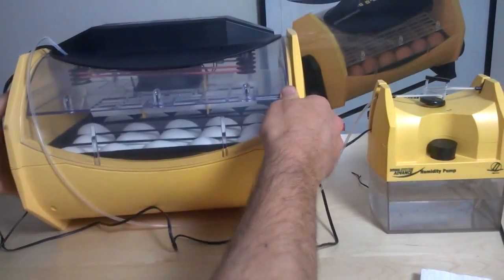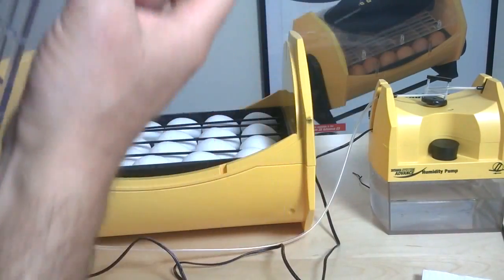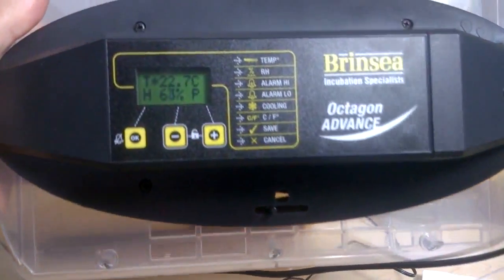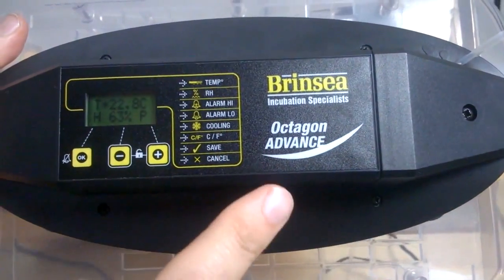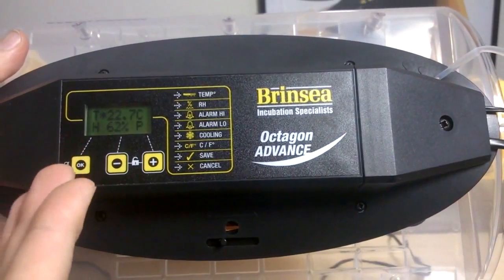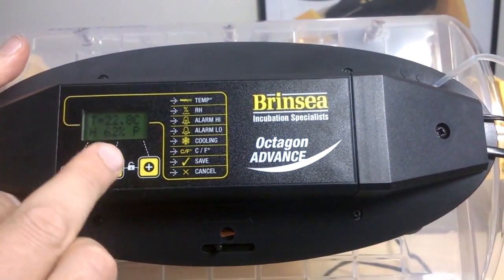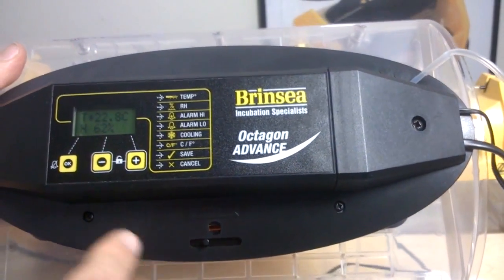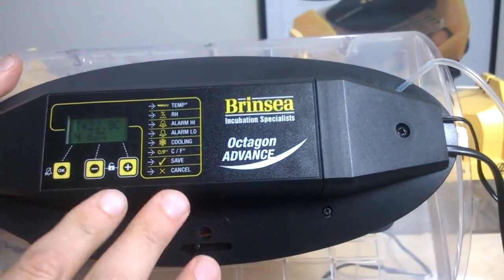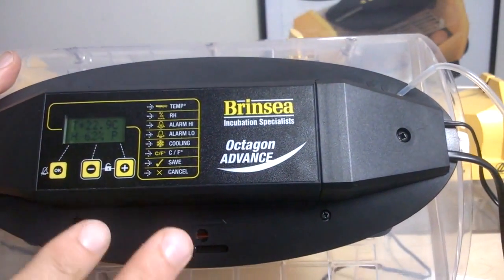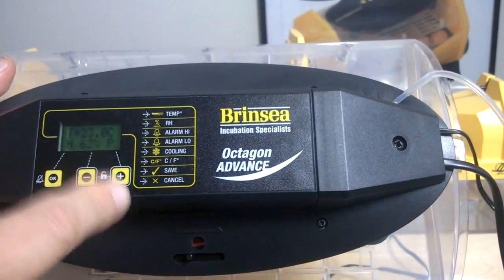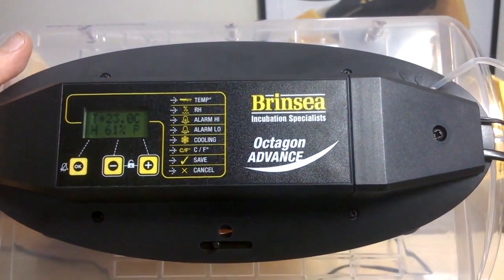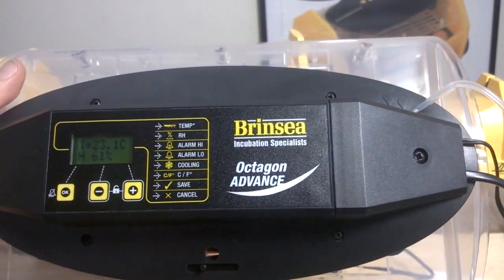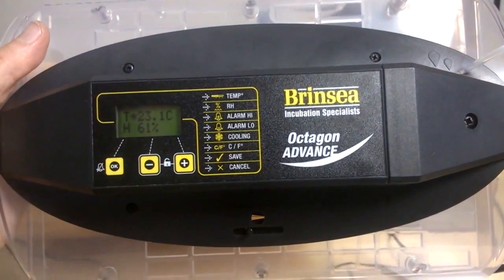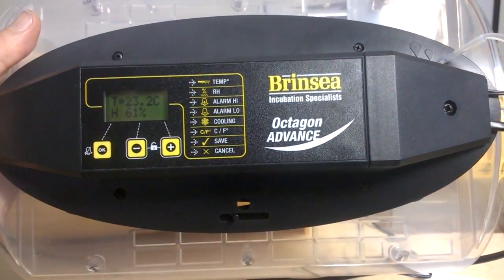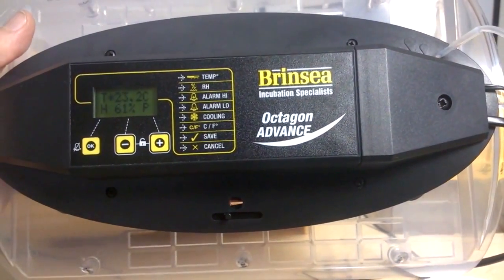So what I would need to do now, the machine having started, is I'd need to wait until the machine has stabilized. So it needs to come up to temperature, and when it's come up to temperature, I can then adjust my humidity on it. I'm going to leave it for a while now to come up to temperature, and then we're going to plug in the humidity that we want that machine to work to. At the moment, it'll be set at 20%, which is the factory default setting for the humidity, and I want to set it to 40% to incubate some eggs.